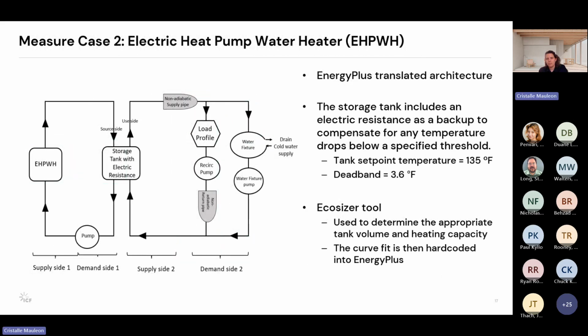This slide is showing the Energy Plus translated architecture for measure case 2, which models a split system electric heat pump water heater with a swing tank. The system includes a storage tank with electric resistance backup to model the swing tank, and it activates if the water temperature drops below the set point of 135 with a 3.6 degree deadband. Just like in the baseline and measure case number 1, both city and recirculation water flow into this tank, which is heated by the electric heat pump water heater.